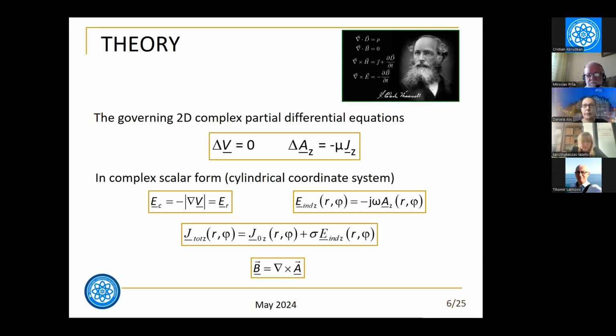Since the explored cable has no ferromagnetic parts and the current inside the cable is harmonic, the complex domain can be adopted. The calculation of the complex total current distribution across the cable's cross-section could be determined applying analytical methods, but the solution is quite complicated, and the current density vector dependence on the distance from the cable's axis is in the form of Bessel functions. For this reason, the calculations described in this paper were performed numerically applying the COMSOL Multiphysics computer program based on the finite element method.